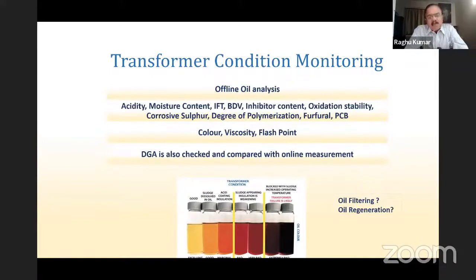And there were sudden transformer failures, and on investigation it was found that this DBDS was the culprit. Nowadays each transformer oil is tested to avoid this corrosive sulfur. Then color, viscosity, flash point, etc. And DGA is again rechecked offline to confirm with the online measurement that it is correct.